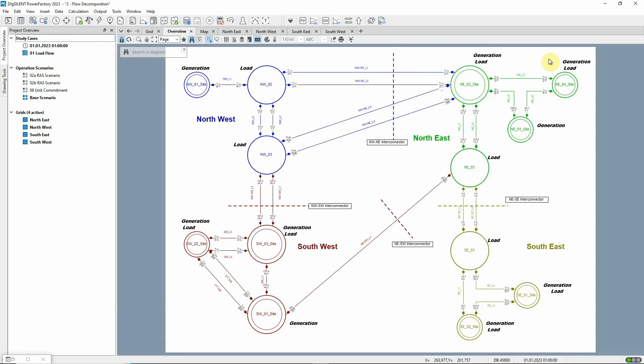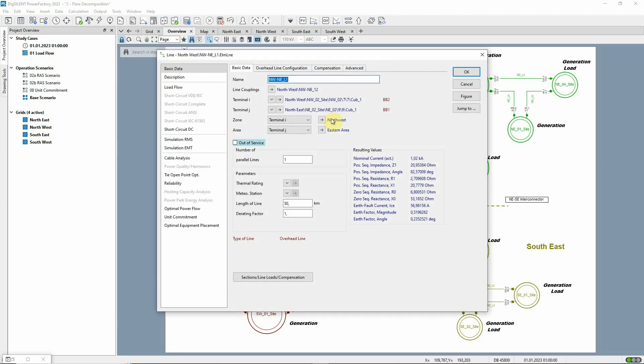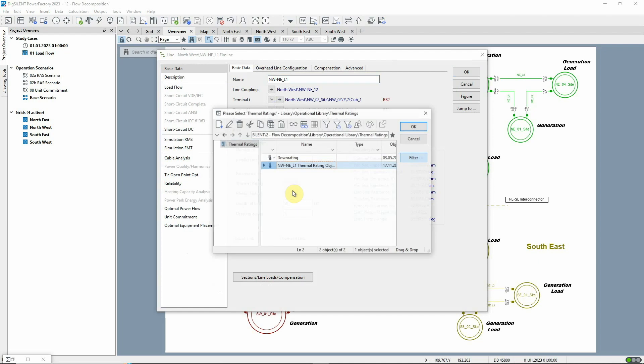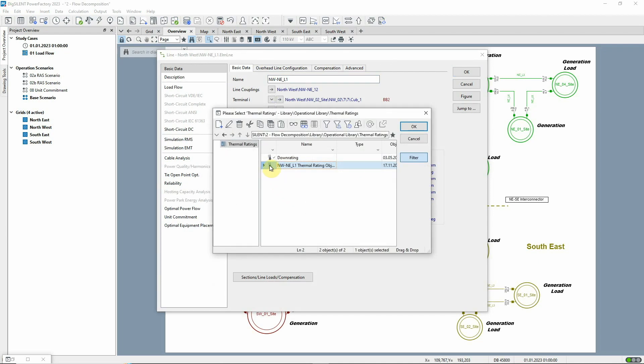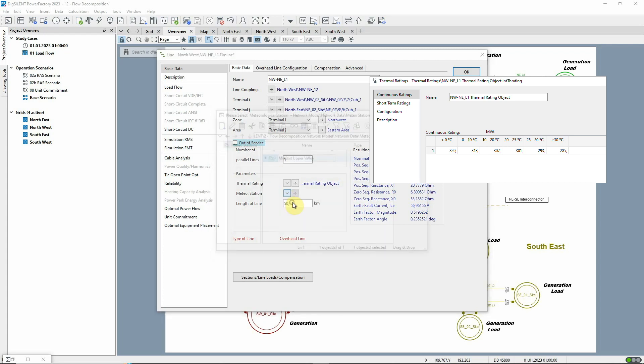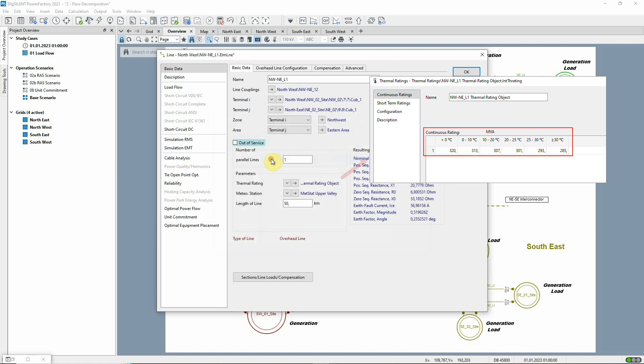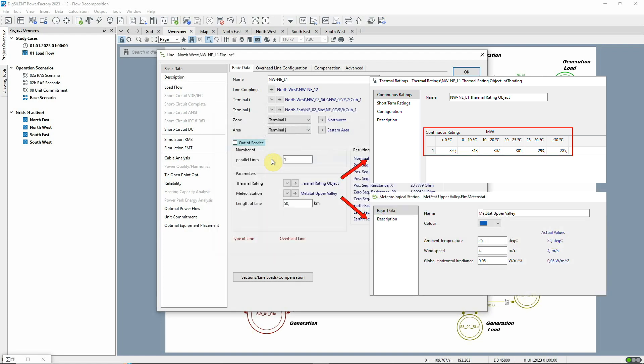In a separate development relating to circuit loadings, the thermal rating object has been enhanced. Thermal rating objects can be assigned to branch elements in order to model complex rating schedules such as short-term ratings. It's now possible to include weather-dependent ratings where factors such as ambient temperature are supplied via a meteorological station element.